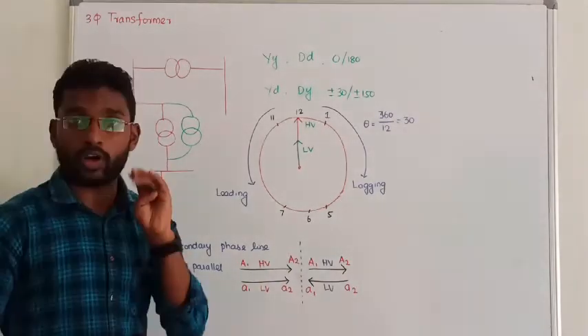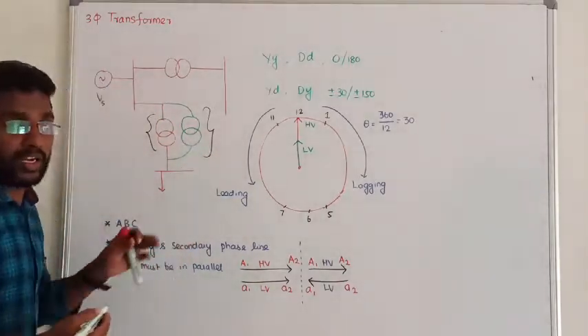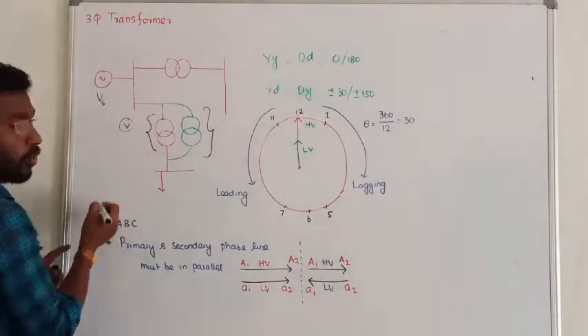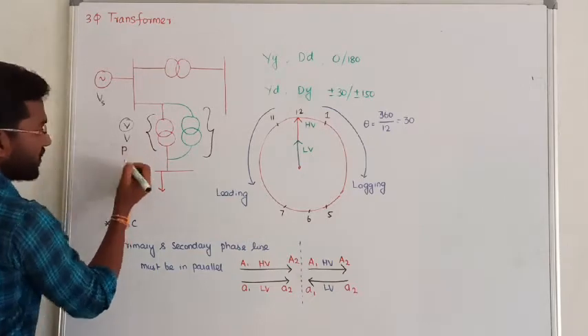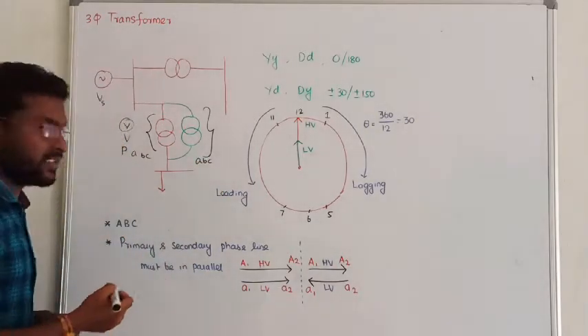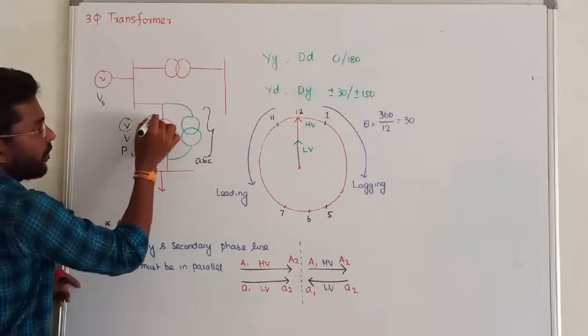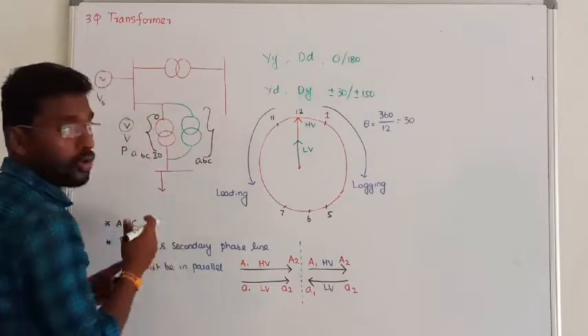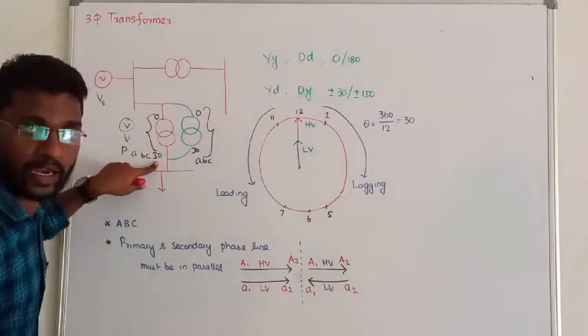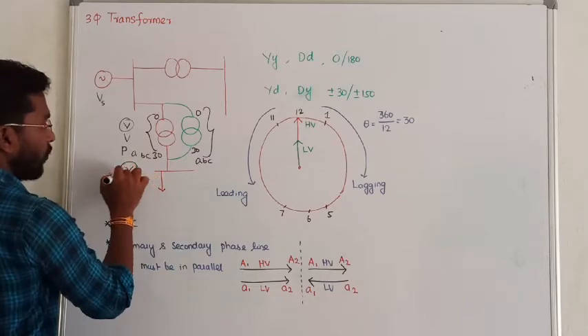The parallel operation concept — we saw four conditions in the three-phase system. If there is a transformer and an incoming transformer, they are going to be parallel connected with the same voltage magnitude, same polarity, same phase sequence (a, b, c), and the phase displacement between primary and secondary must be the same. These four conditions are mandatory while performing three-phase parallel operation.